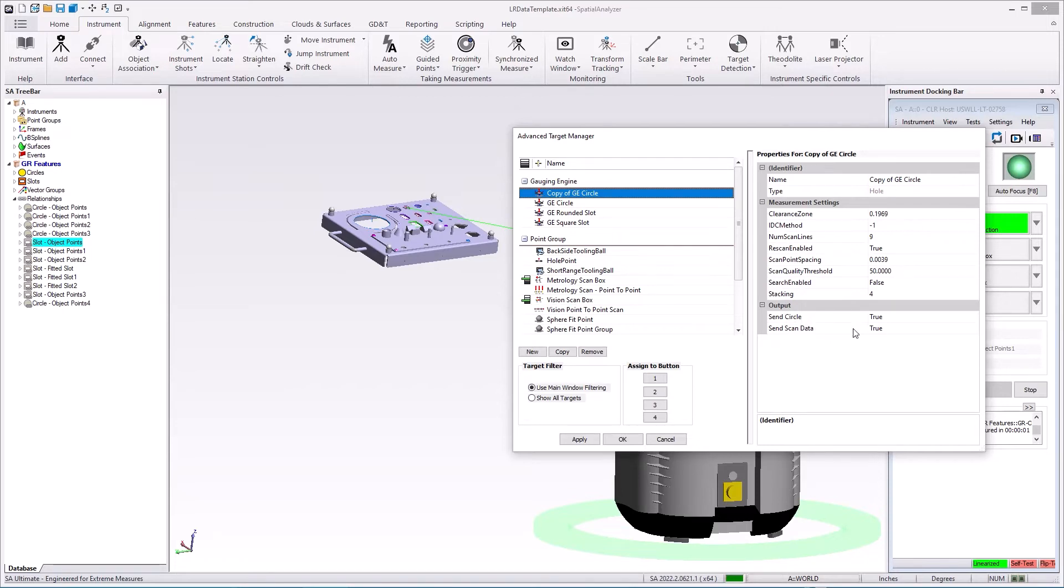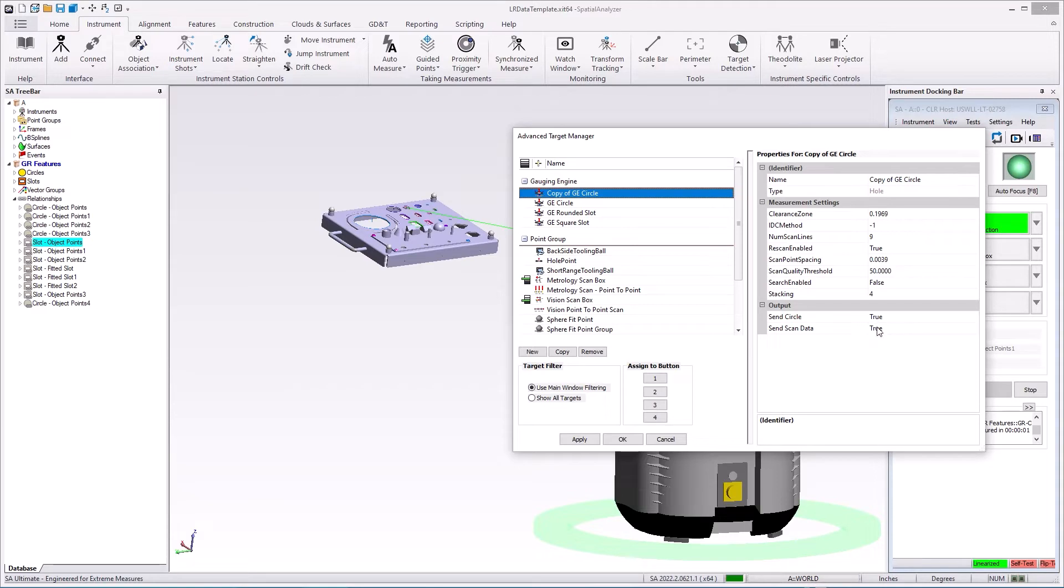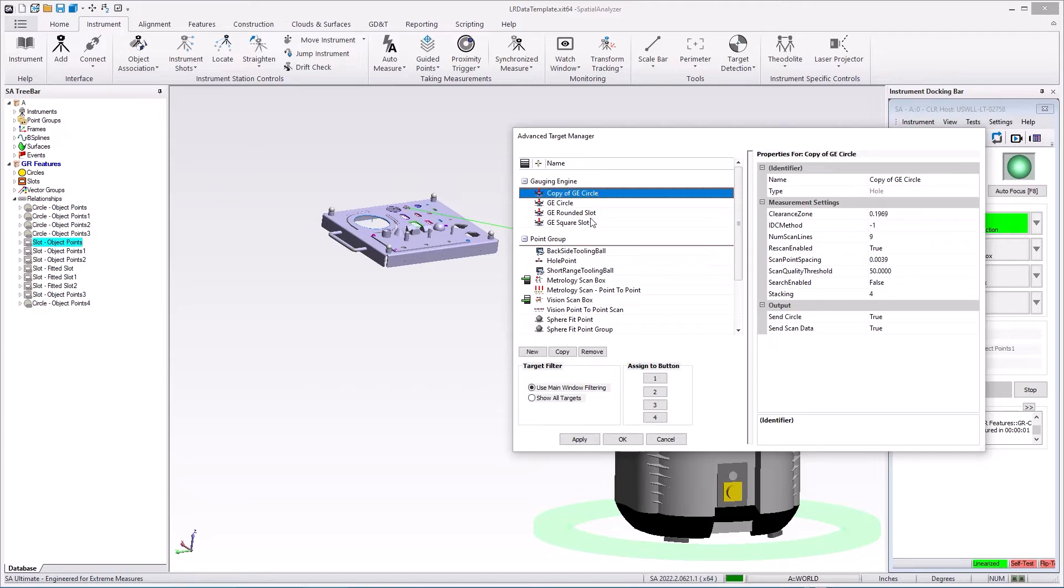The circle is extracted directly as part of the analysis on board the instrument and can be sent to SA. You can then send the cloud data or the combination thereof, and I'll just send both. And you can also adjust how it's measured, let's say nine scan lines, or you can speed up that process and change the spacing. So all these controls are now inside of this gauging engine to a target definition.